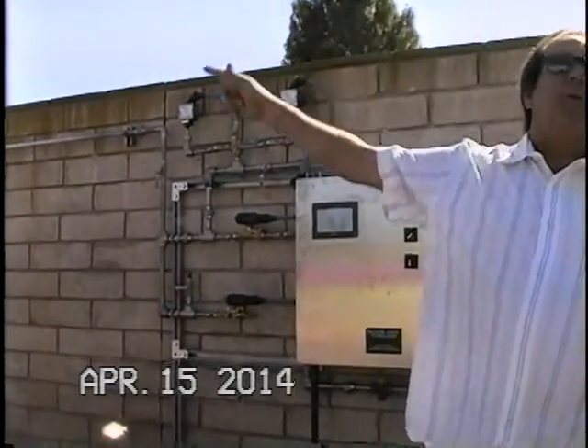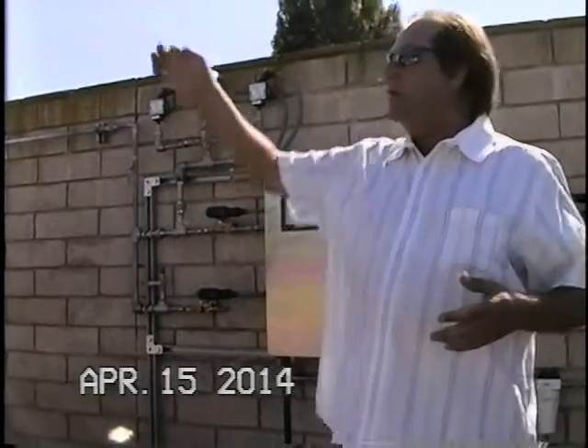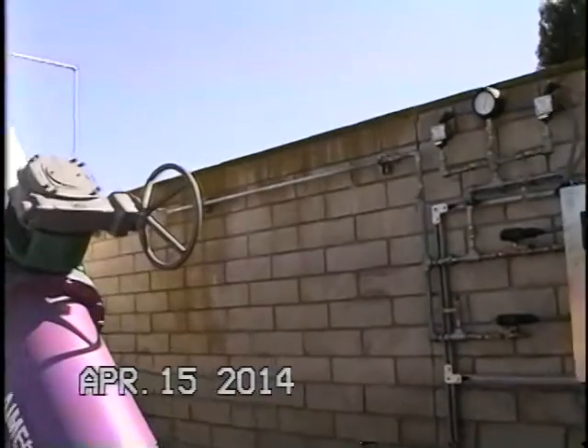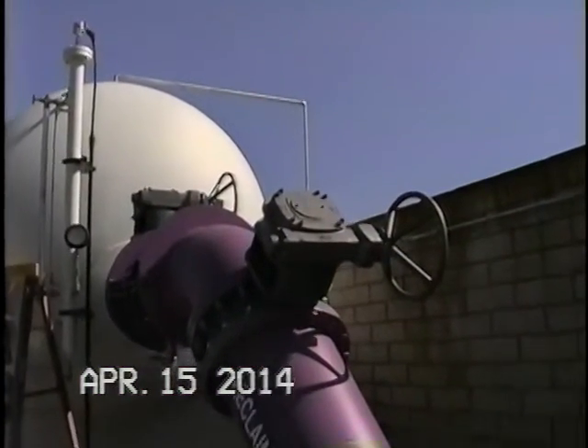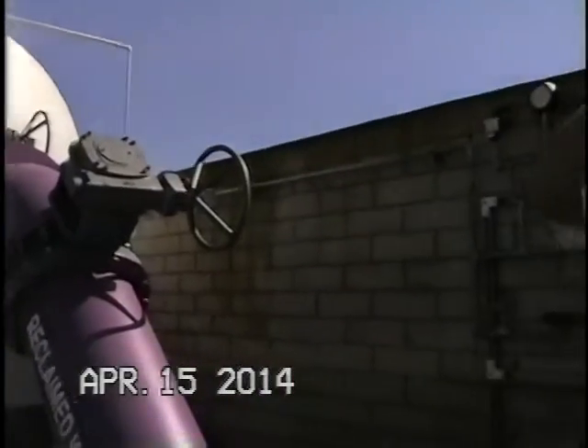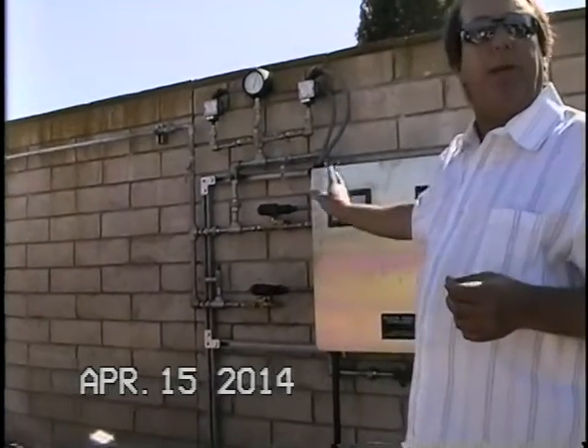What we have is, we refer to them as RF probes, though they're really a capacitance probe. It's made by Endress+Hauser. It's a single half-inch diameter rod that goes the full length of that probe well, and it senses the water level by the different conductivity between the air and the water, and it turns that signal into a 4 to 20 milliamp output. In a lot of cases we have conductive probes where individual probes have individual operations. Well, in this case, we're taking that 4 to 20 milliamp signal and sending it to our control panel, and it's being processed through a PLC.